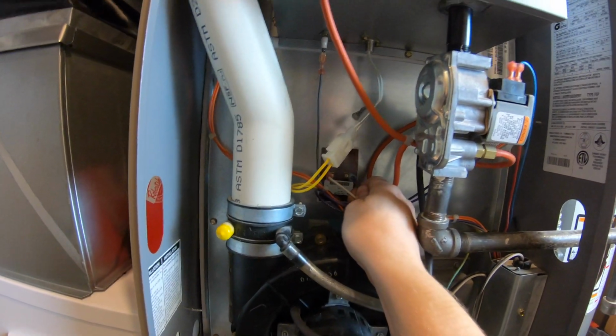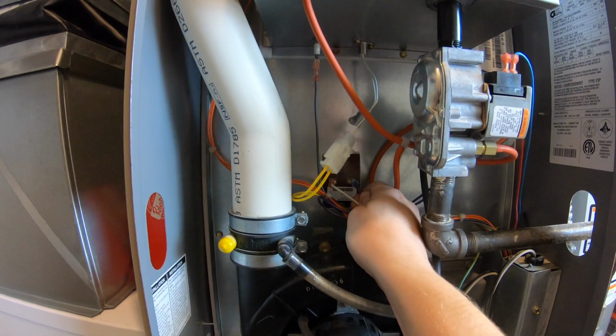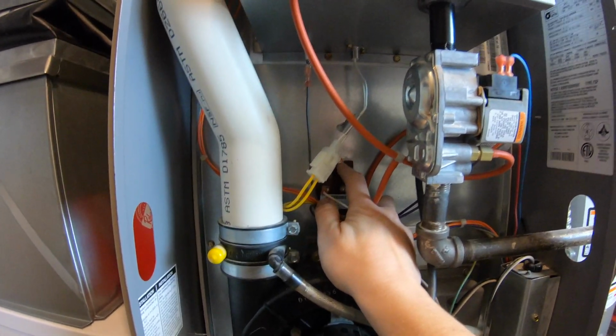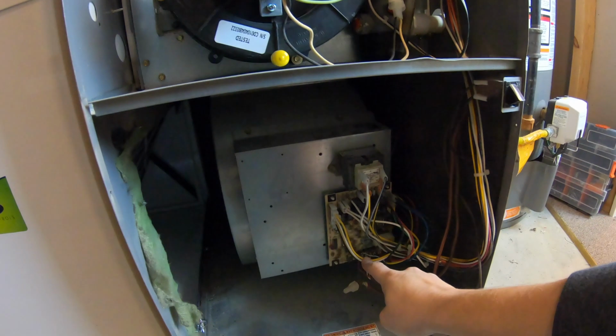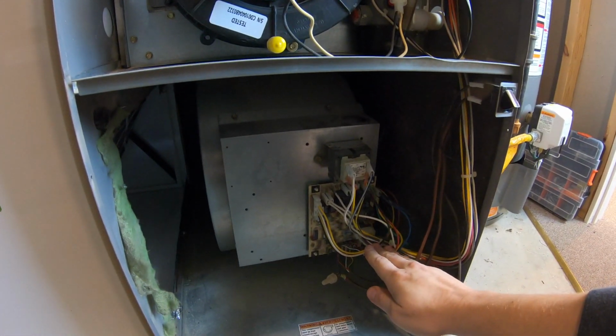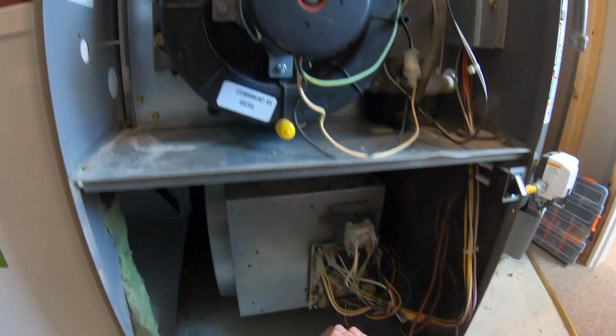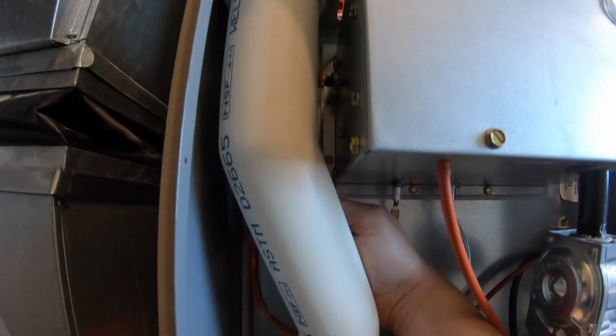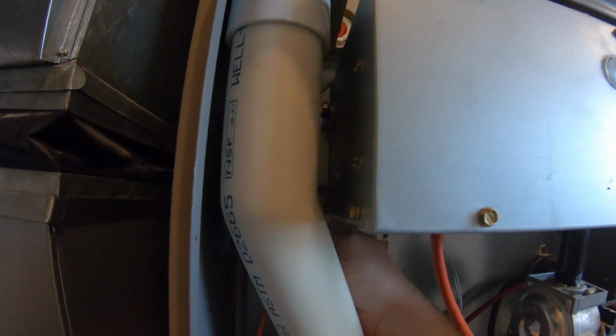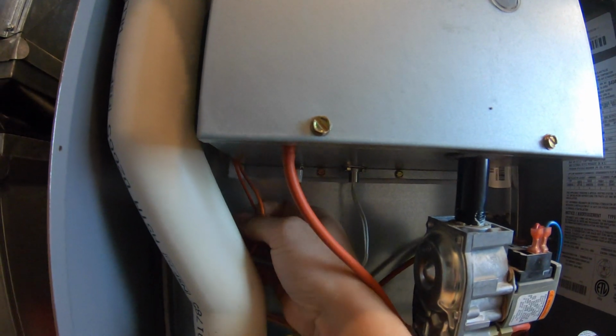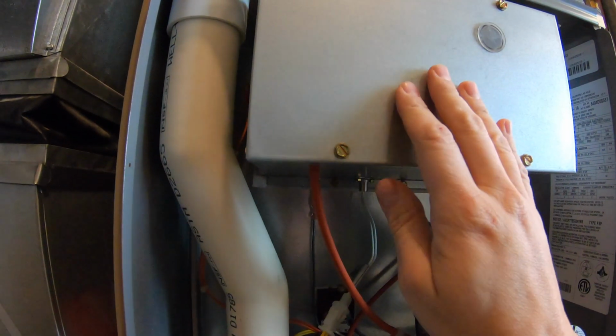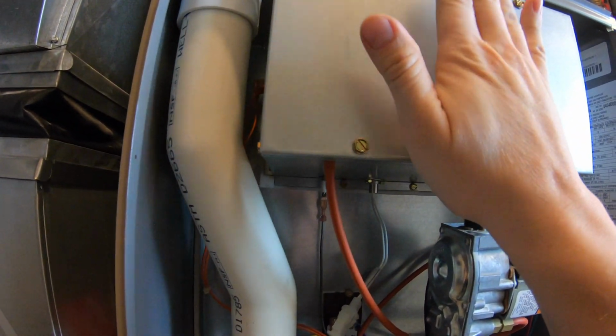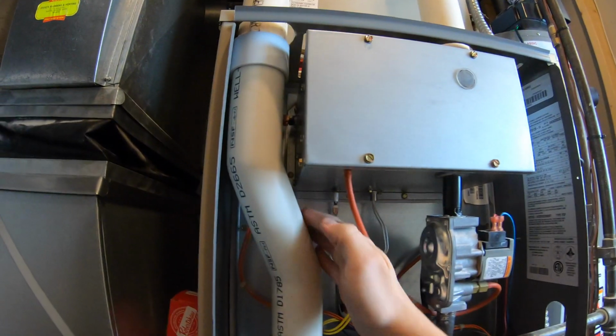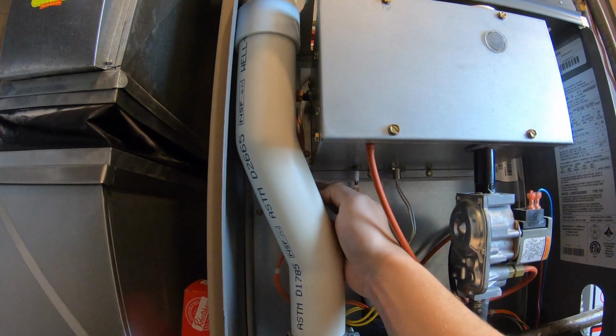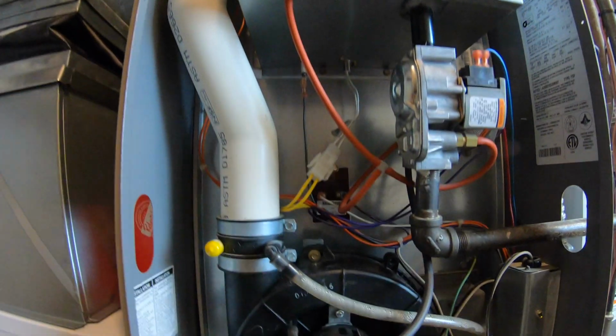So there's 24 volts going through this switch all the time. Unless it gets too hot, then it will break that circuit and tell the circuit board to turn off the burners because it got too hot. That is an important safety device. And then this one right back here, if you can see it, is a rollout switch. So if for some reason the flames inside of the burner compartment are making this burner compartment too hot, or if you've got flame rolling back from inside the heat exchanger, that will cause the burners to shut off as well as a safety device.